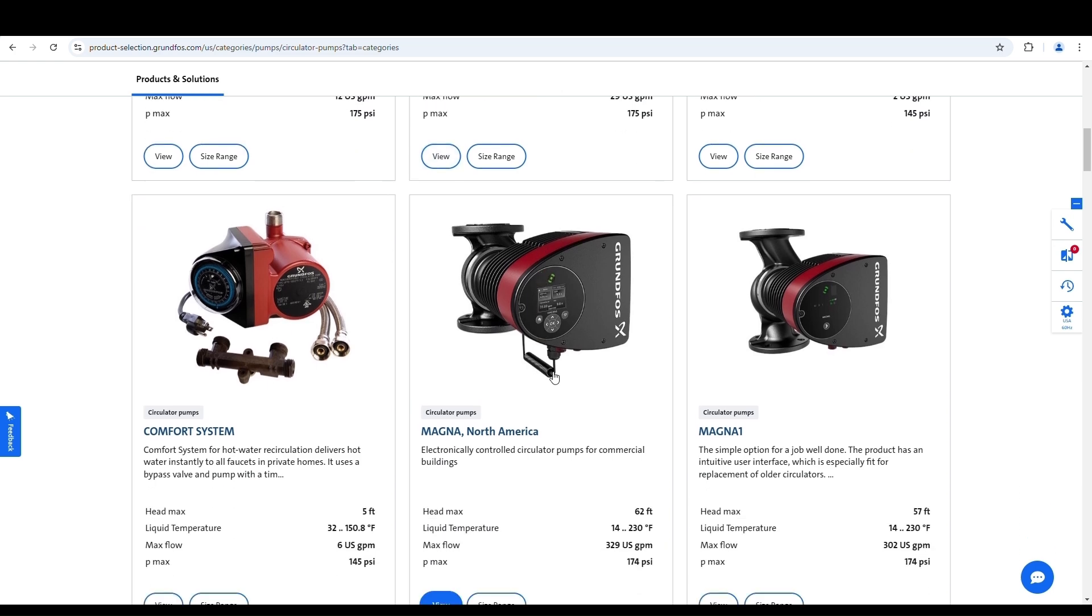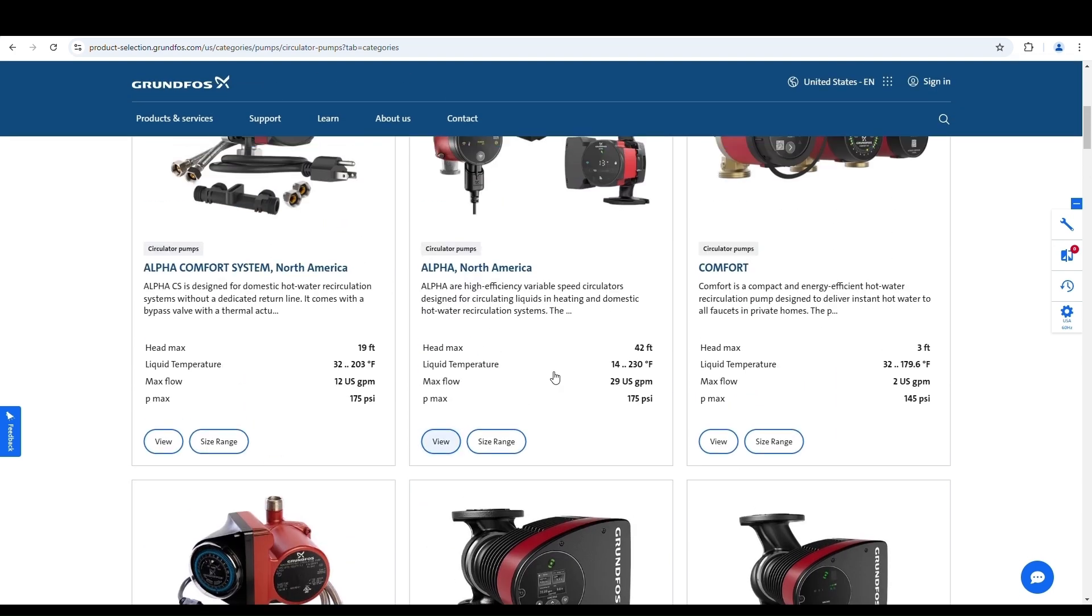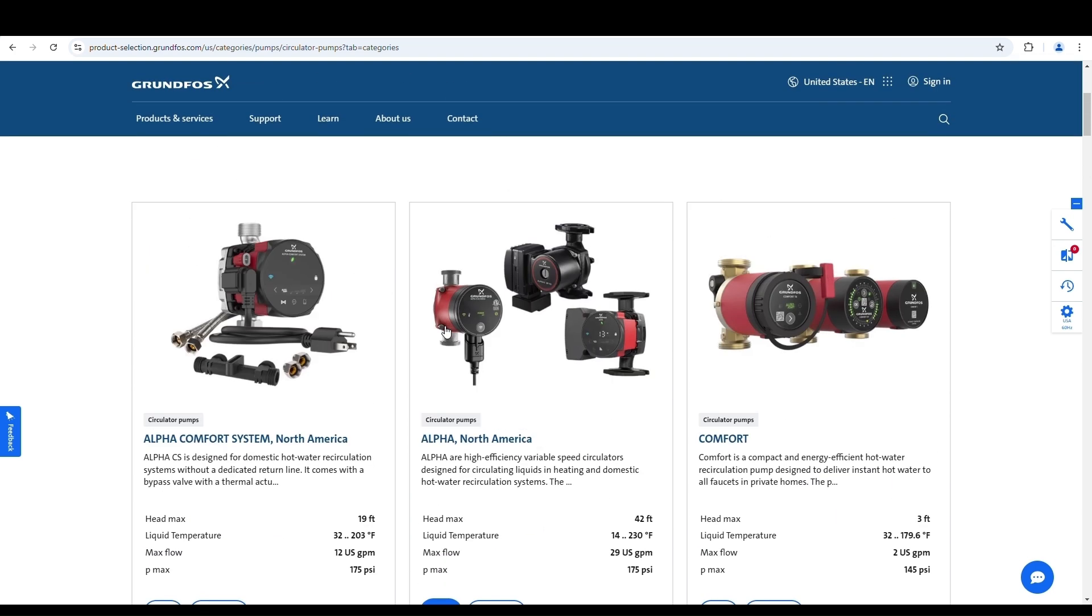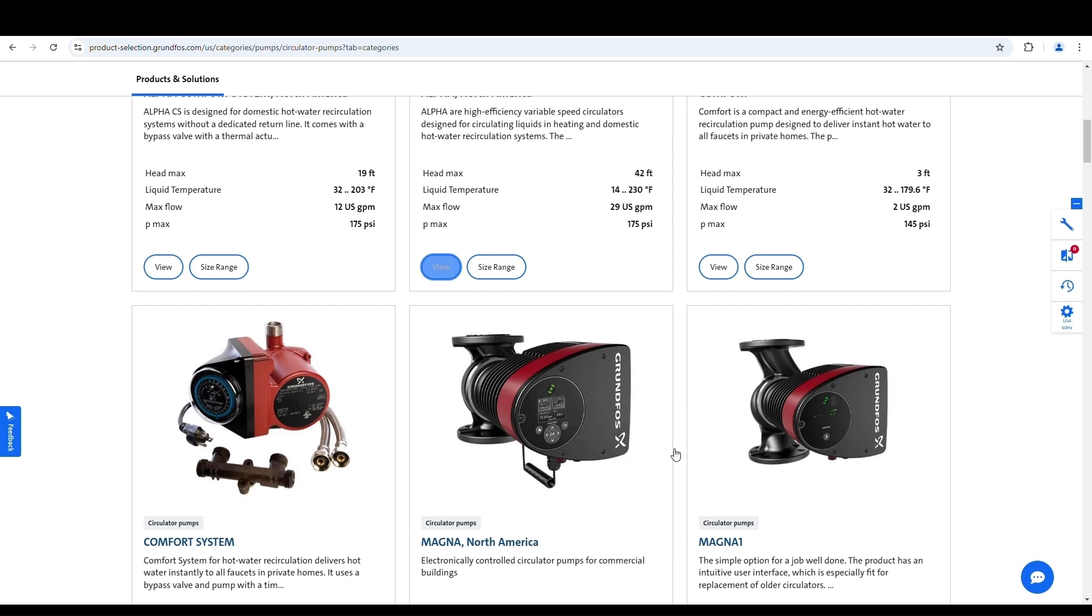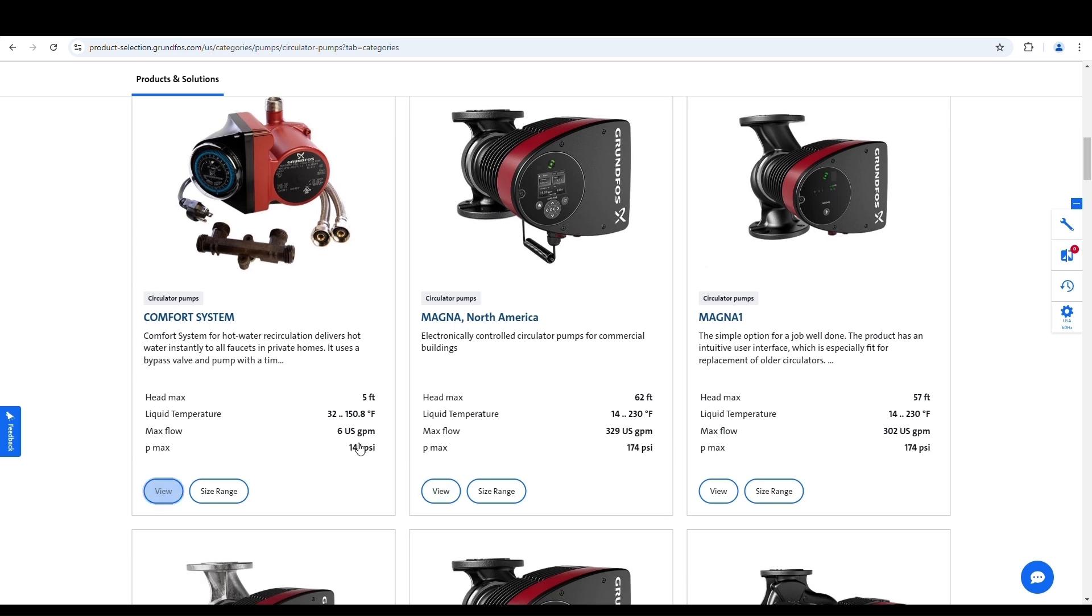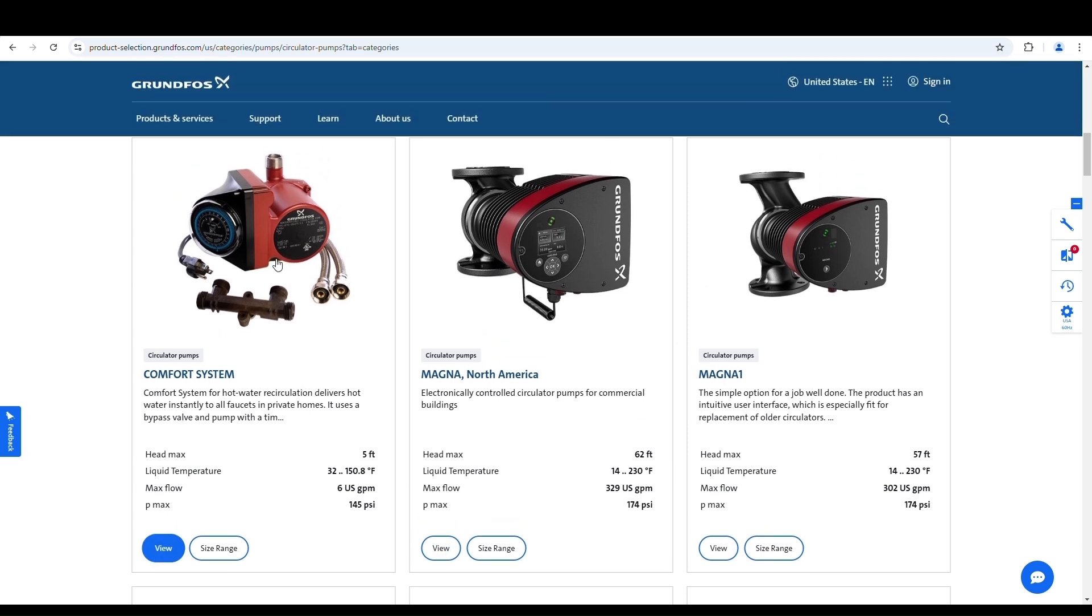There's one thing you've got to be very careful about: look at the flow rates on here. See here, US 12 GPM, 29 GPM, this one's only 2 GPM, and then 6. You'll find, see, this one here, this is a typical hot water circulating pump, but see the max flow is 6 US GPM. Well, here's the thing. If I go over to...